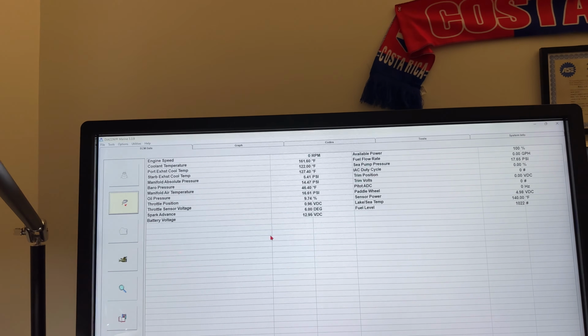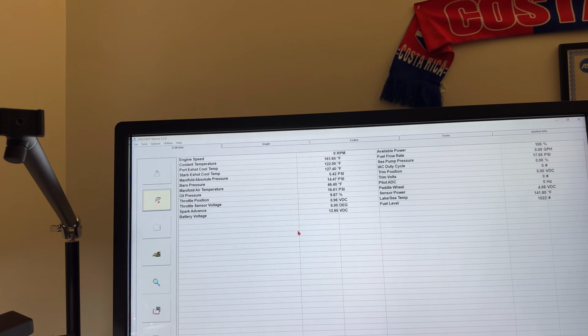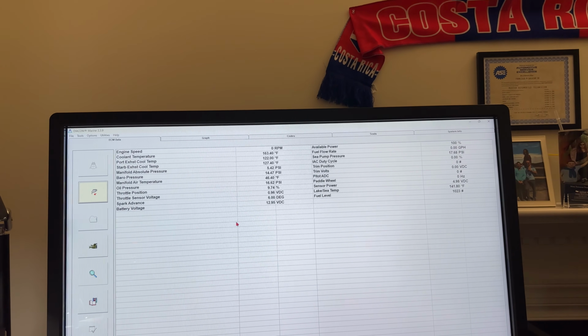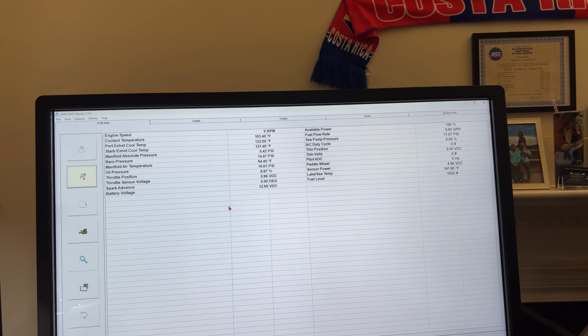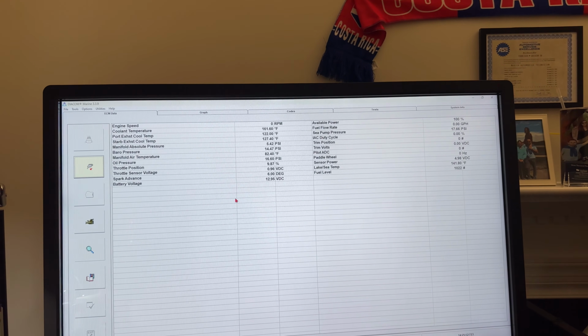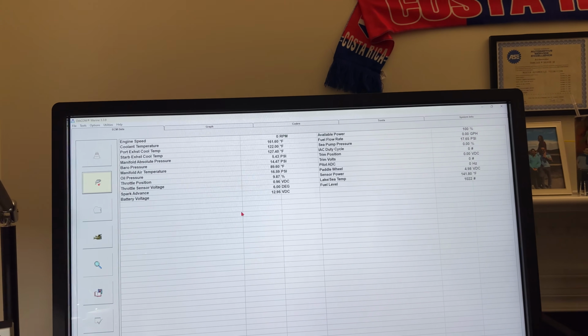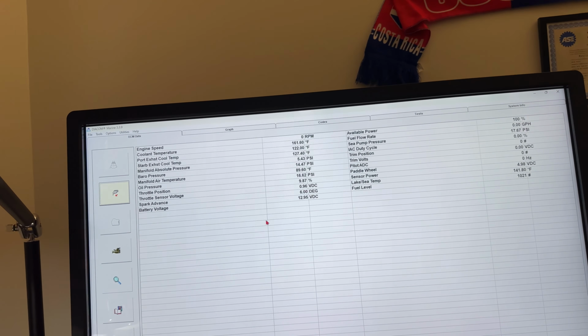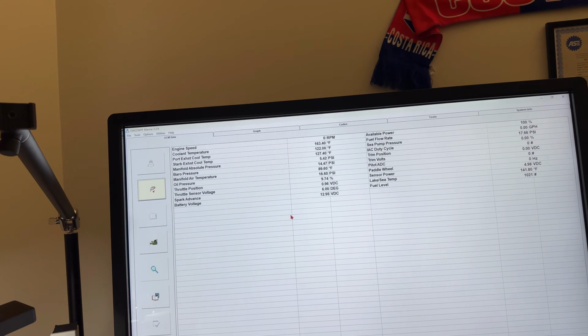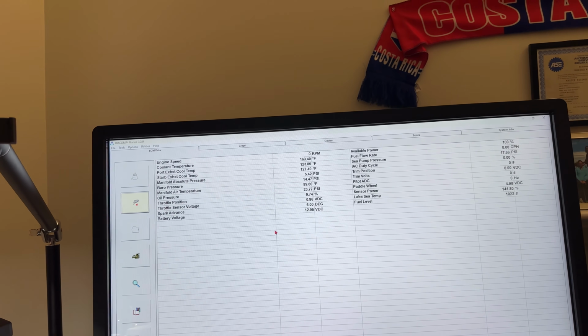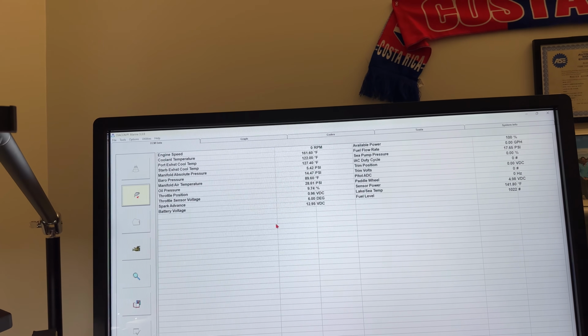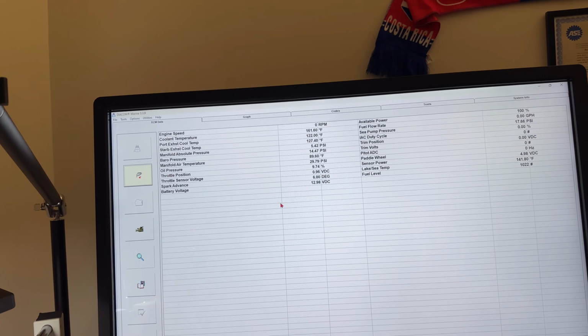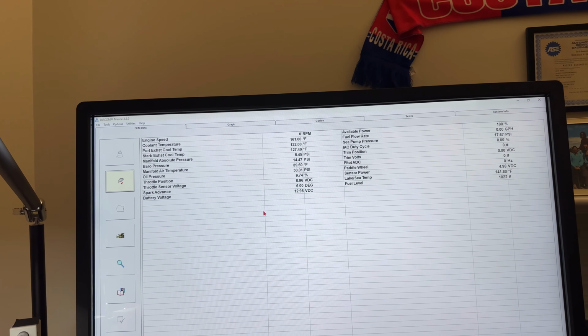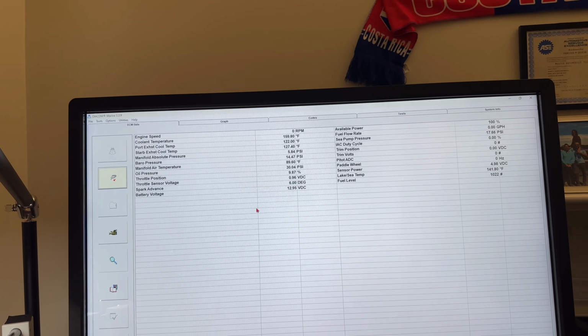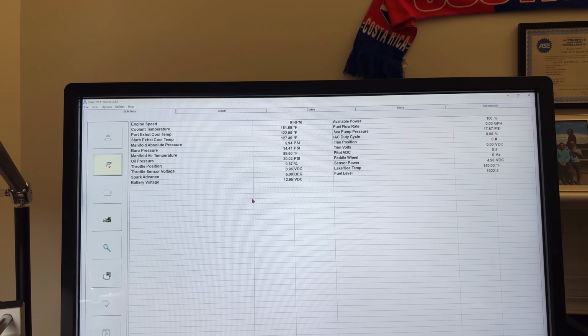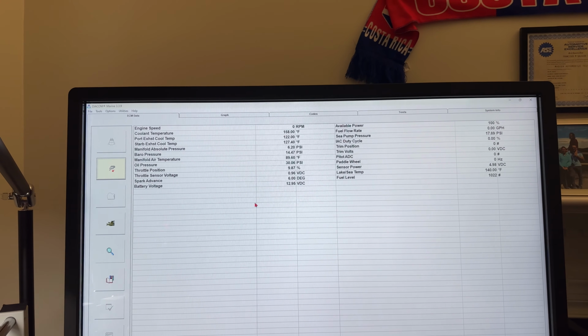So I like to keep it around 160. The manifold air temperature isn't that important to me, but we can raise that to 70 or 100 degrees if we want - anywhere around there is fine. The oil pressure is a little low, so I'm going to raise that to around 20 so we get 100% power when the engine is running. I like to keep this around 6.1 psi for cranking.